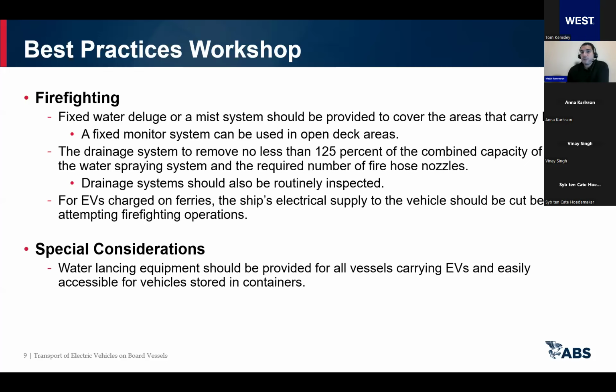To ensure safety in areas carrying electric cars, it is essential to install a fixed water deluge system or mist sprinkling system. For open deck areas, a fixed monitoring system can also be used. The drainage is to be capable of handling at least 125% of the combined capacity of both the water spraying system pumps and the required number of fire hose nozzles. Required routine inspections are crucial for the drainage system to prevent any clog or blockage.